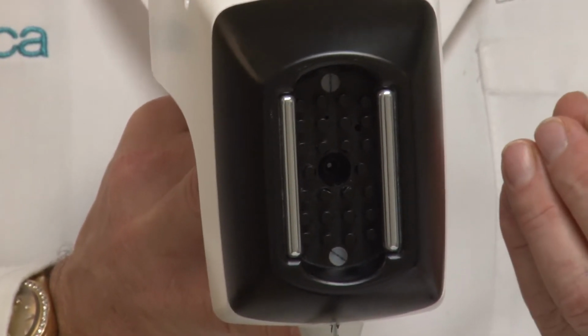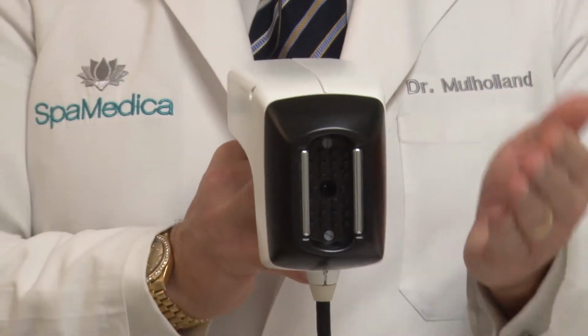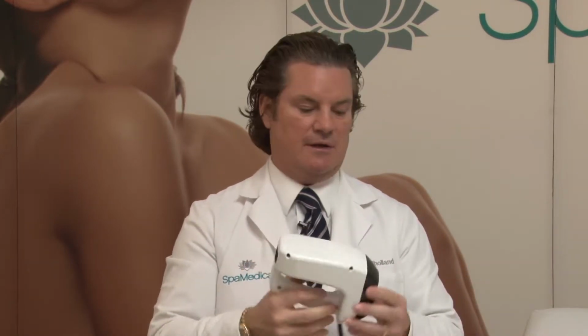Thermally controlled RF delivery. When it gets to the endpoint, remember, basic RF shuts off and second RF, high voltage pulsing, is released. As it drops 0.1 degrees Celsius below your thermal endpoint, boom, on comes the first RF again, heats it up. When it gets to the endpoint, second RF's delivered. So you want to get to the endpoint of 44 degrees, and then you start counting. 10 minutes per area, divided into 5, 5, 5, and 5. So 20 minutes of treatment time per tissue zone. Each zone is measured again, 2 hands. Okay? Very easy to use, very ergonomic. There's no rollers, no elbow and shoulder workman's compensation claims. Very simple to use. Okay?